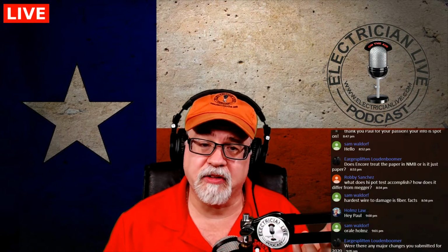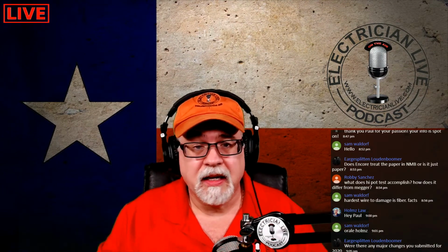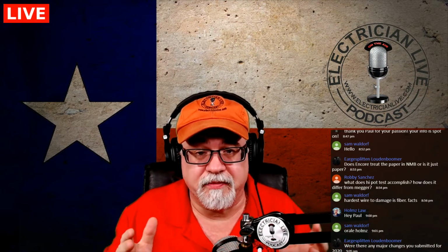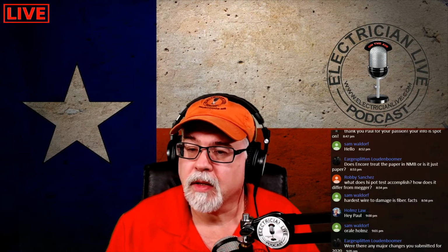And the other thing about it is, with a high pot test, that's it. It's destructive. It's either a pass or fail. Meg test, you're getting a reading, and it's non-destructive. With a high pot test, if there's something wrong or there's some damage, it's gone. You with me? It's a pass or fail for that. Let me catch up here. I got to go through some other tests.